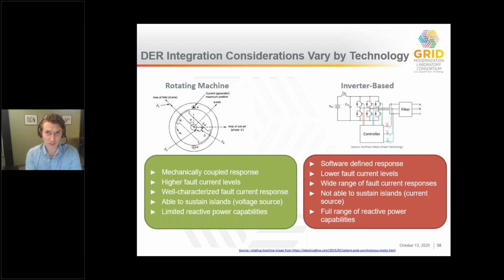I've sort of boiled this down into two main types. We have rotating machines on one hand, and these are sometimes called synchronous generators or induction generators, and they physically have a rotating mechanism within them that is using electromechanics essentially to produce power. So it has a mechanically coupled response that's related to the speed of that rotation.